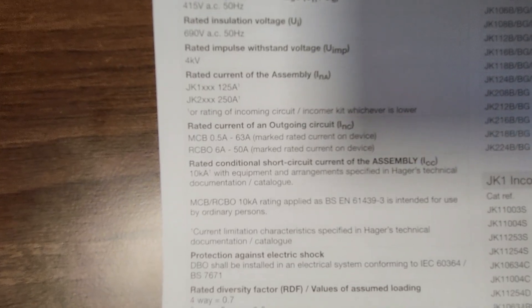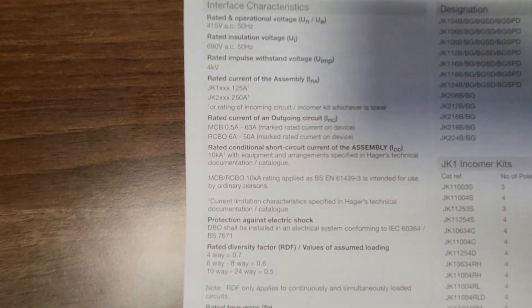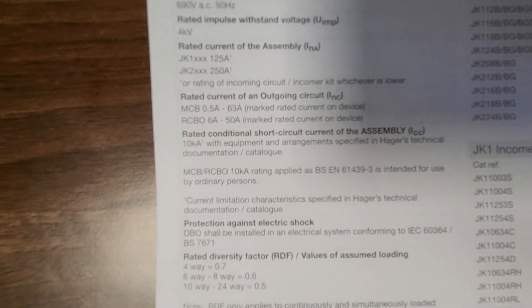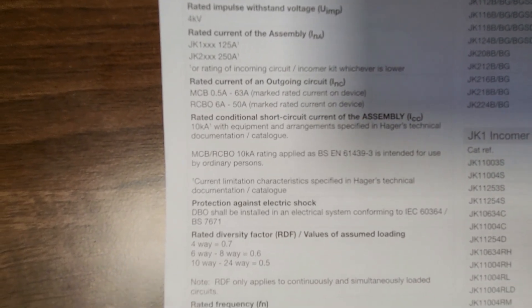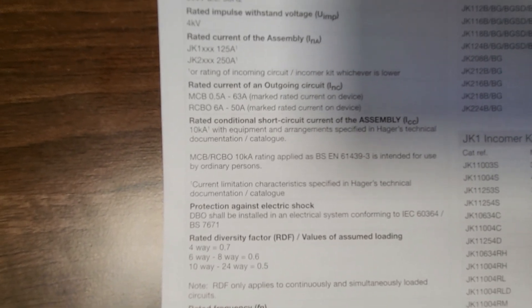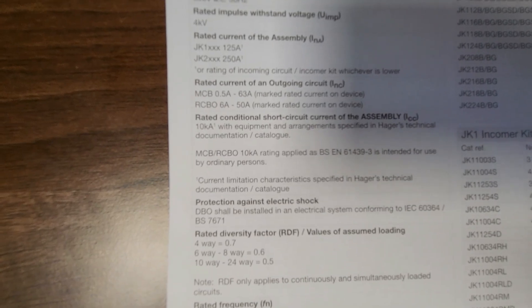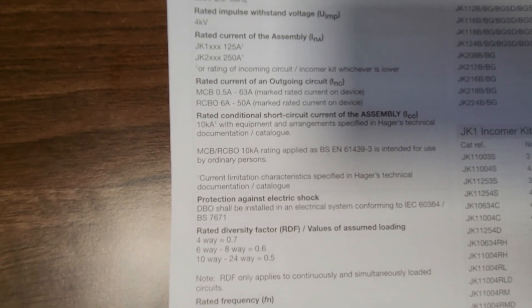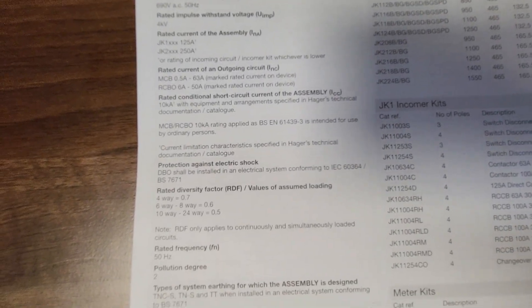You've then got your outgoing circuits — your MCBs going down to half an amp should you wish, all the way up to 63 amp. And RCBOs are 6 amp to 50 amp. The rated conditional short circuit current of the assembly as a whole is 10kA with equipment arrangements specified in Hager's technical documentation catalogue. RCBOs and MCBs have a 10kA rating. You can get these in a 15kA range and then they do comply — some of these MCBs comply with both BS EN 60898 and BS EN 60947-2.